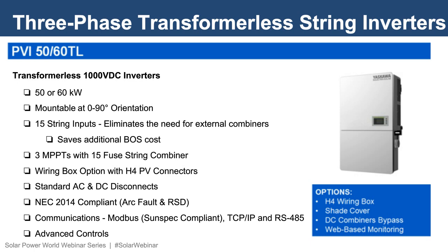Similar to the other products in this family I just talked about, these units have integrated AC and DC disconnects, allowing you to comply with the NEC 2014 and 2017. These units come standard with integrated arc fault circuit interruption capabilities and industry-leading communication capabilities, including SunSpec compliance, remote firmware upgradability, and the ability for the Solectria Service Department to perform remote diagnostics on the units.